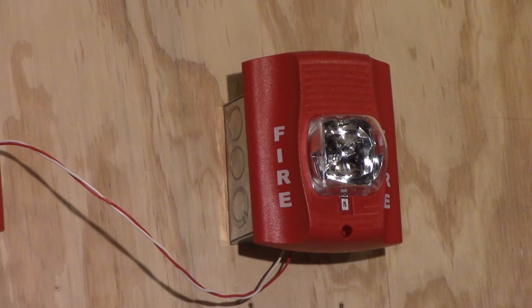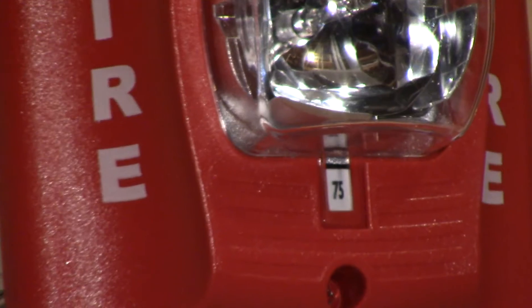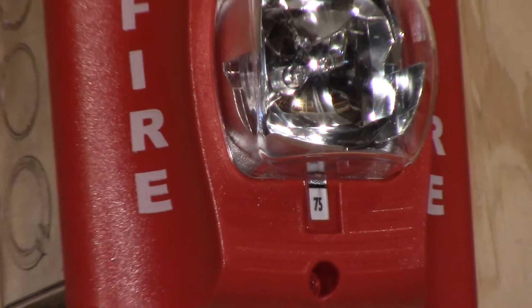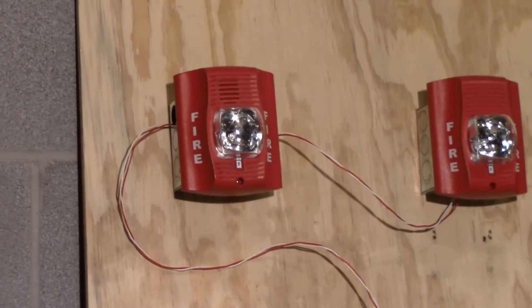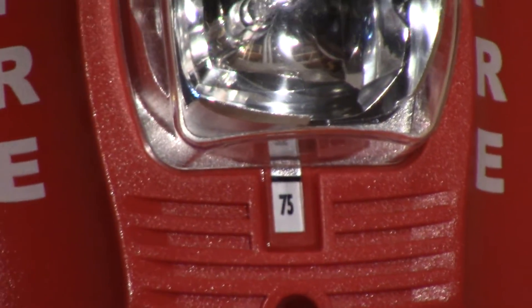Following it up we have a System Sensor SpectrAlert Advance SR Remote Strobe. Right next to it we have my System Sensor P2R SpectrAlert Advance Horn Strobe, set to Code 3 Medium Volume and also set to 75 Candela.